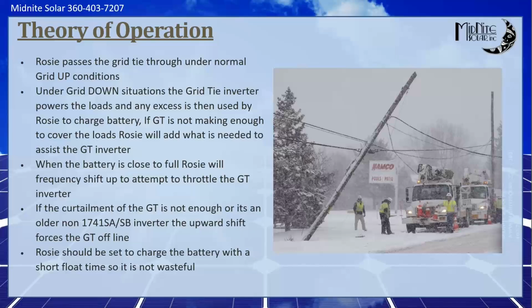So let's say it's a day like this and it's snowing and the grid tie inverter is making 500 watts and the load is 3,000. The Rosie will power 2,500 from the battery. But now let's say the sun comes out and the grid tie inverter is making 7,000 watts and the load is 3,000. The Rosie will take 4,000 watts and put it into the battery after the loads are satisfied with the first 3,000. So it uses everything it has; the loads are priority, I guess is the way to say that. Loads first, battery second when you're AC coupled.